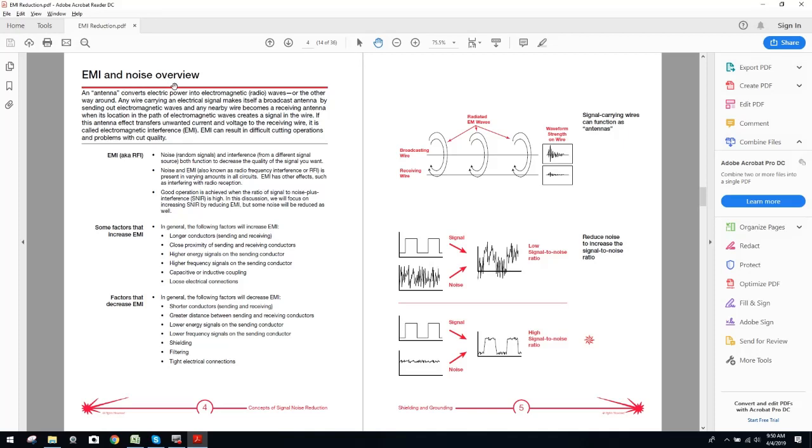Okay. EMI noise overview. Real simple. An antenna converts electric power into electromagnetic radio waves or the other way around. Any wire carrying an electrical signal makes itself a broadcast antenna by sending out electromagnetic waves and any nearby wire becomes a receiving antenna. When its location in the path to the electromagnetic waves creates a signal in the wire. If this antenna effect transfers unwanted current and voltage to the receiving wire, it is called electromagnetic interference, EMI.